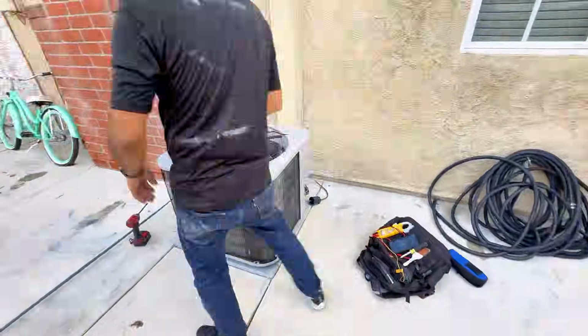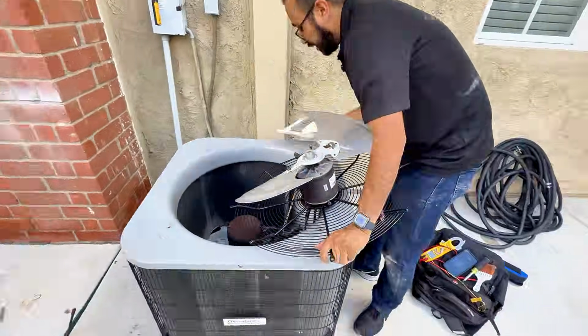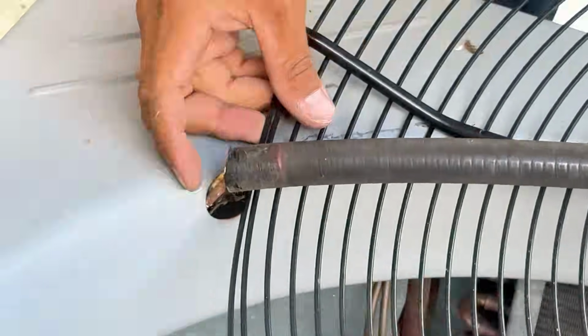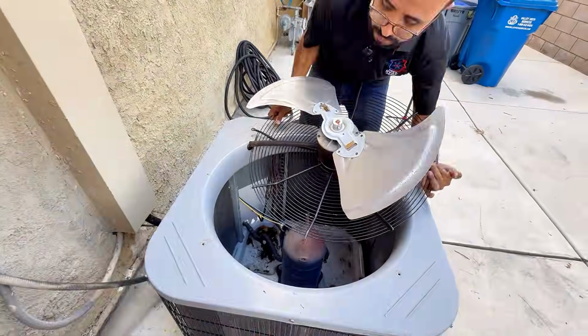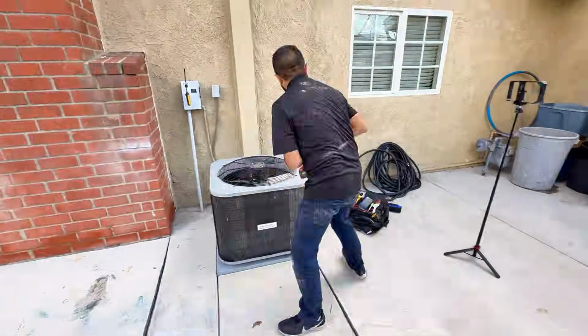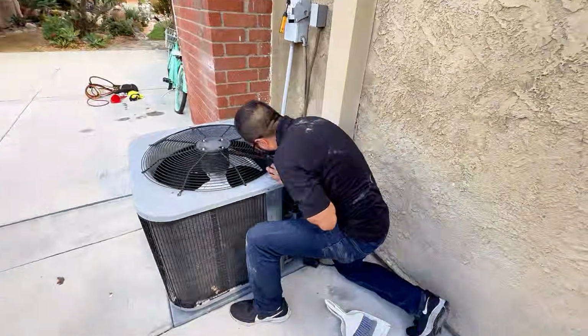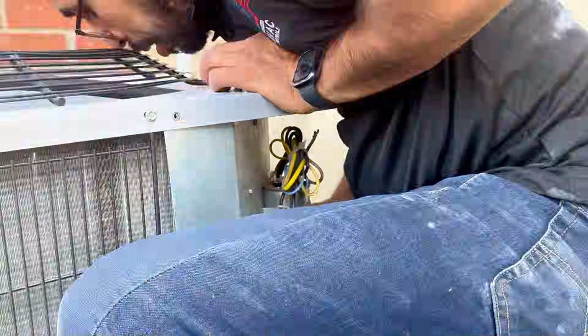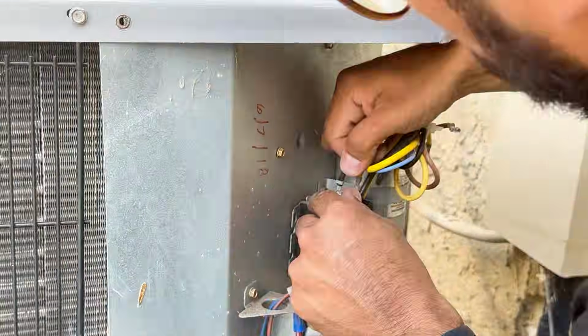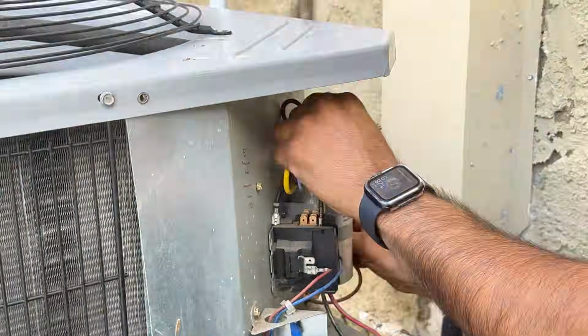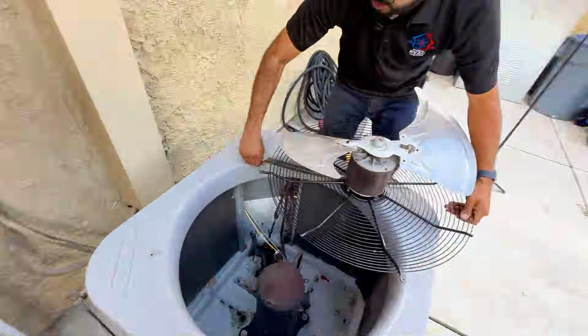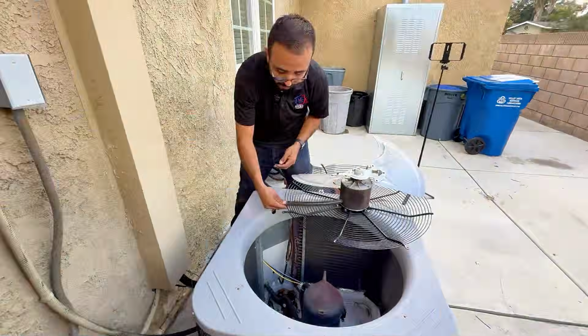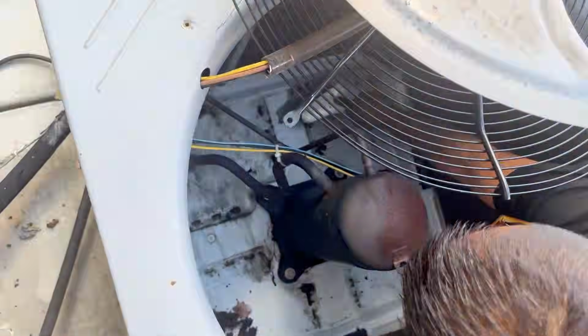At this moment I'm removing the condenser fan. I ensured the disconnect is off, which I already confirmed. I noticed my wires going to the condenser fan were pretty tight. Some guys like to remove those wires completely and take off the condenser fan, but I was able to just loosen up the wires, getting more slack, as you can see.